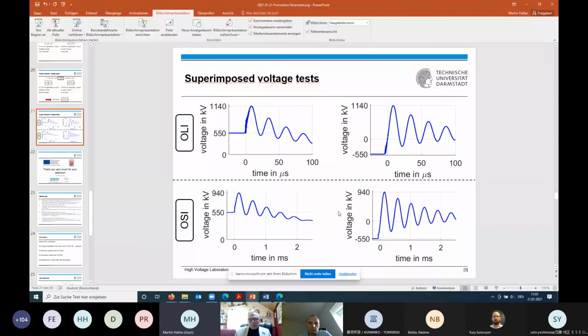And also when you have it not far enough and too close, then during this process you can also get some refiring of the spark gap. Perhaps the second question goes in the direction of whether something extinguishes because of the oscillations. We have made many tests with oscillating impulse voltages, and we have never observed this effect. Even when you have zero crossings in your voltage shape, you do not have a spontaneous extinguishing during the testing. So this I can share as information.